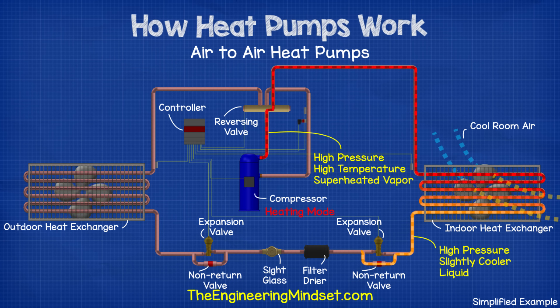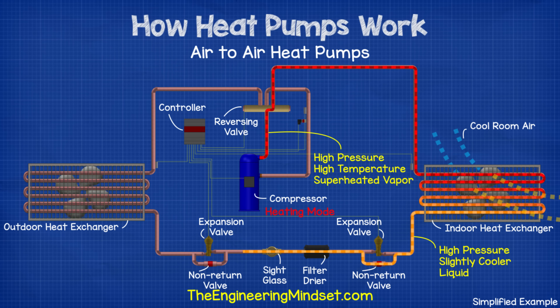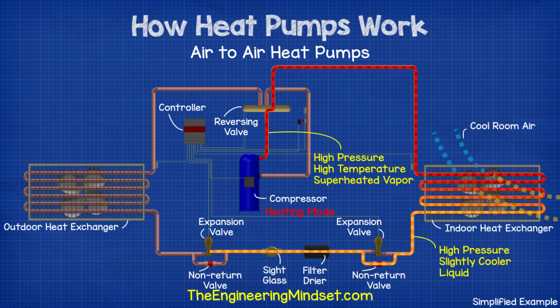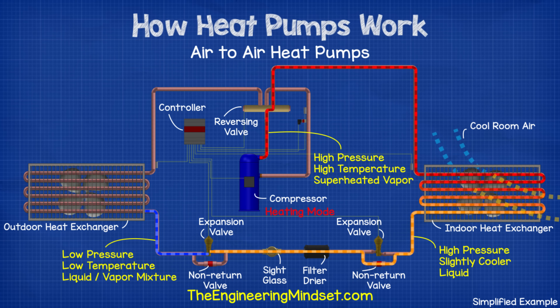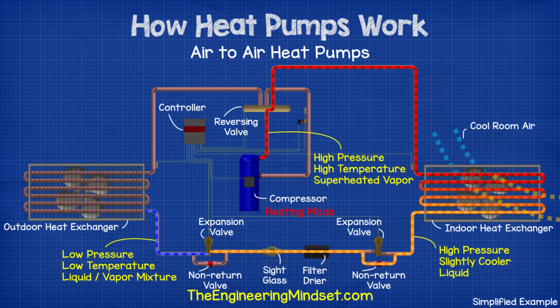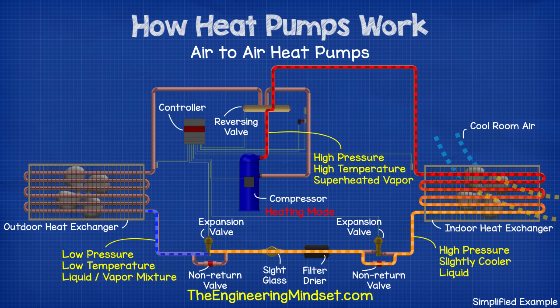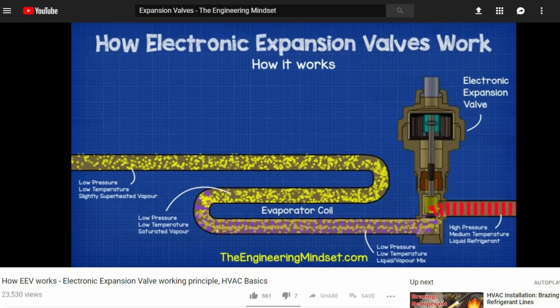The refrigerant then comes to the expansion valve and bypass. In this mode, the expansion valve is closed, so the liquid refrigerant passes through the non-return valve. It then passes through the filter dryer and sight glass, and then passes to the second expansion valve. It will then pass through this expansion valve because the non-return valve on this side is preventing flow in that direction. As the refrigerant passes through the expansion valve, it expands in volume and turns into a part liquid, part vapor mixture. This expansion in volume reduces the temperature and pressure. We've covered how thermal expansion valves and electronic expansion valves work in great detail in previous videos — links are in the video description below.